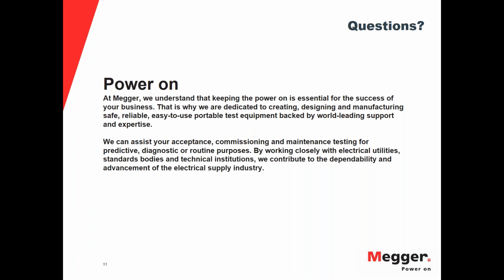All right, next question. Can the battery charger alone supply all the DC loads momentarily? Is it acceptable to supply all DC loads with the charger only, say, for 1 hour without the backup or standby battery connected? So yes, the battery charger is supposedly capable of supplying the entire load of the substation, and that's what it actually does under normal operation. The charger is supplying the load, and it's supplying a little bit more so it can maintain the charge on the battery. So that's what the floating condition is, that it will supply voltage and current for the load and the battery at the same time.